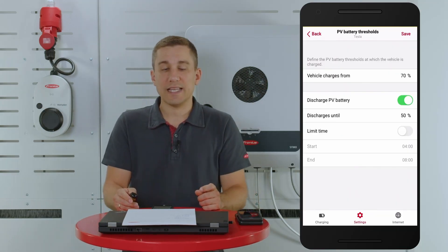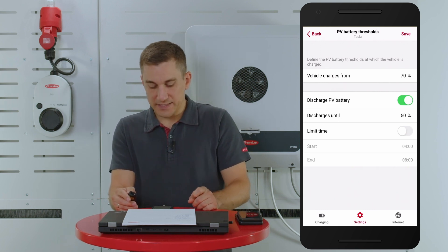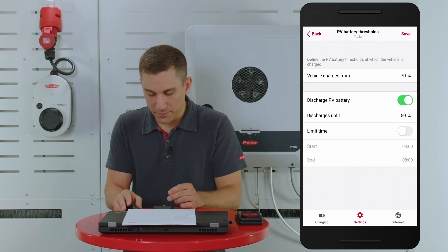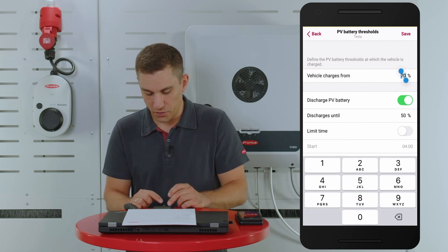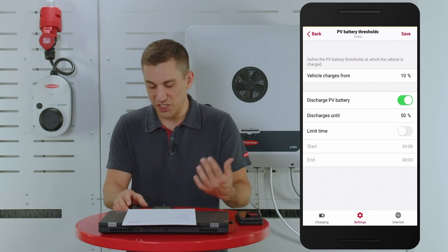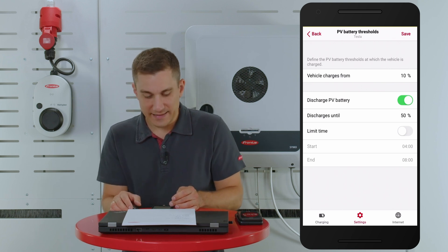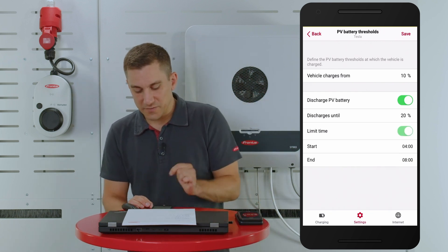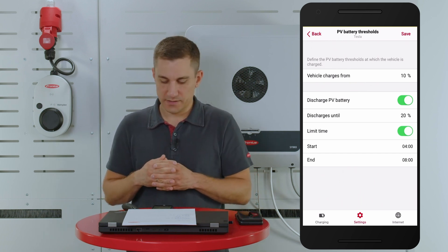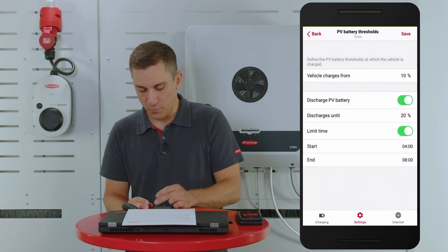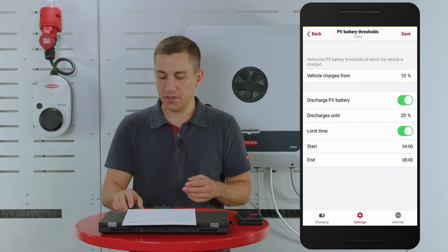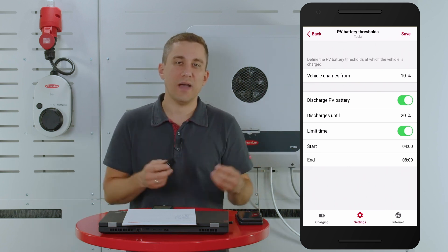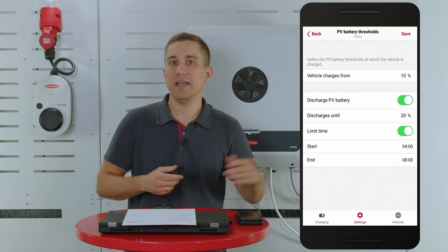The second example is to use time thresholds for your charging and discharging behavior. Besides SOC limits, you can also set a time limit for your system. In this example, we set 'vehicle charges from 10%,' so the vehicle gets charge when the stationary battery SOC is at 10%. We also set the PV battery discharge to 20%. Additionally, we set a time limit — for example, 4am to 8am in the morning. This is useful when the customer knows they need to leave the house at 8am and wants the stationary battery discharged to the lowest possible value so it is ready for the next day to absorb PV energy.